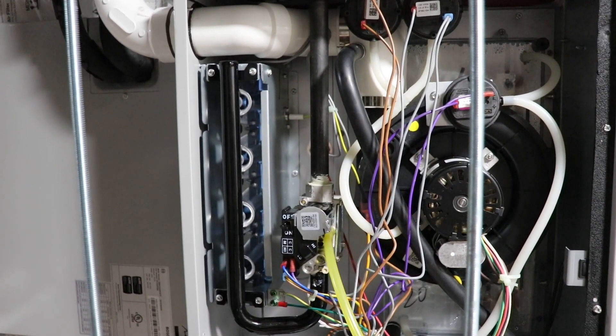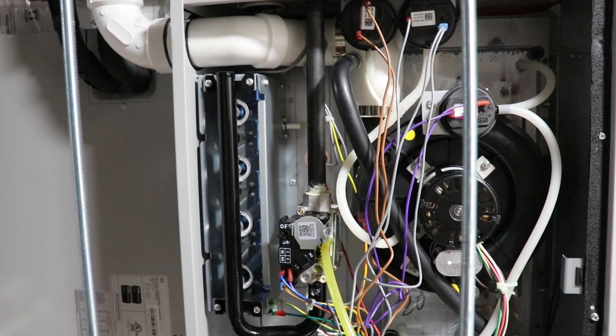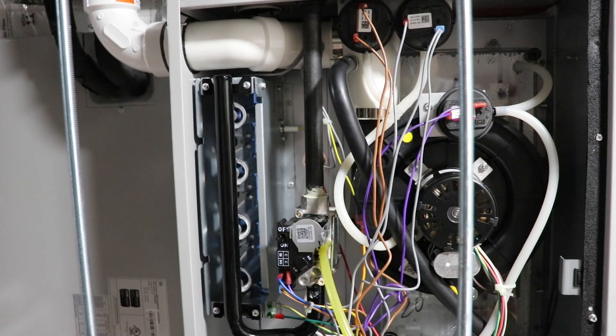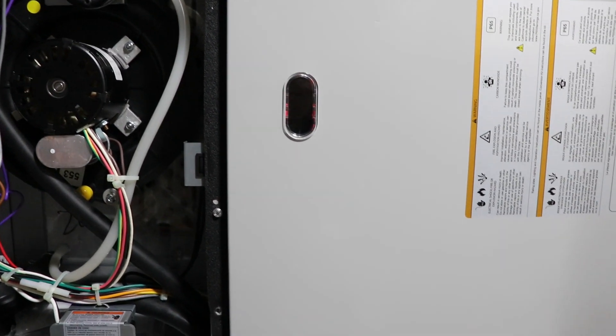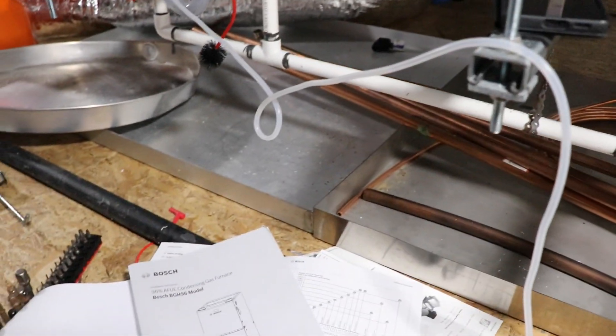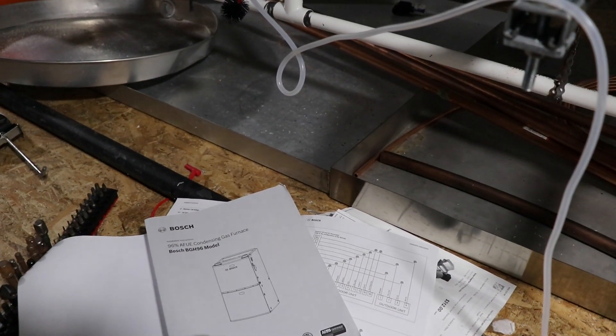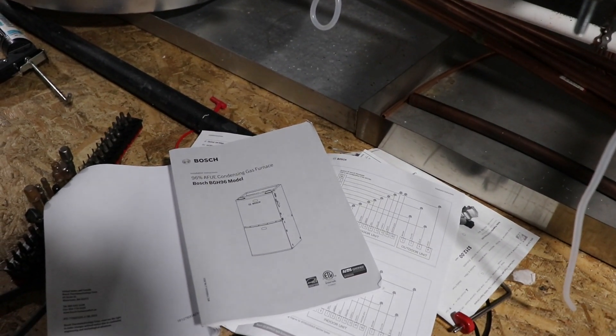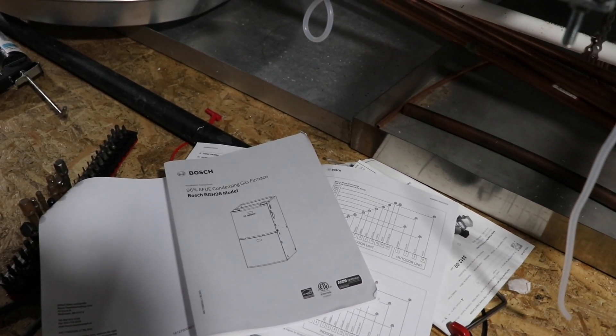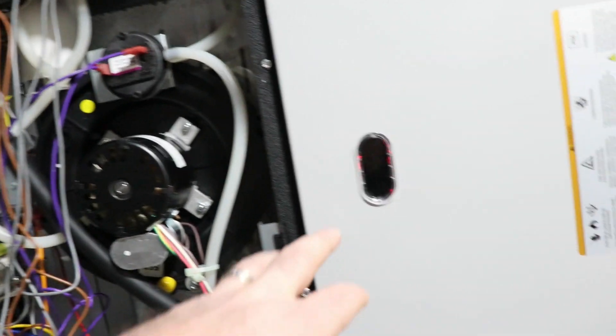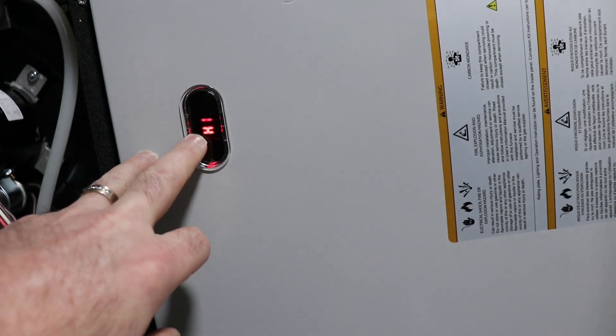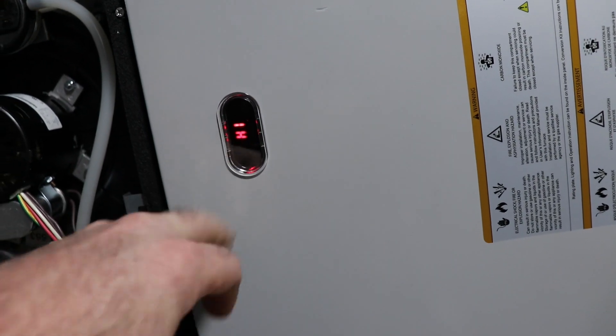If you trip out on E5 six times, the furnace will lock out and you'll have an E6. It looks like the manual with the Rev B furnaces isn't as detailed perhaps as the Rev A furnaces that didn't have a digital readout. They just had an LED that would blink.